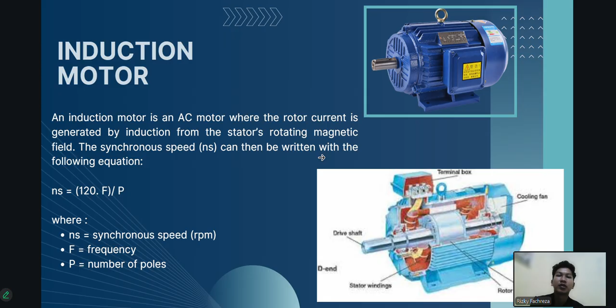The rotational speed of the magnetic field is called synchronous speed, which is formulated as Ns equals 120 times the frequency divided by the number of poles. From this equation, it can be seen that the speed of the motor is highly dependent on the frequency of the power source. That is, if the frequency is increased, the motor speed also increases, and vice versa. This is the main reason why frequency setting is the most effective method to control the speed of an induction motor.